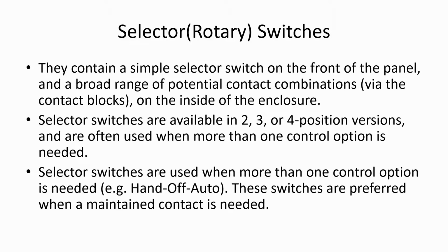So these selectors come in 2, 3 or 4 position versions and are often used when more than one control option is needed, like automatic, manual or off. So if there are multiple options to be selected, then this type of rotary switch can be used. These switches are preferred when a maintained contact is needed. In such applications, these rotary switches are used.